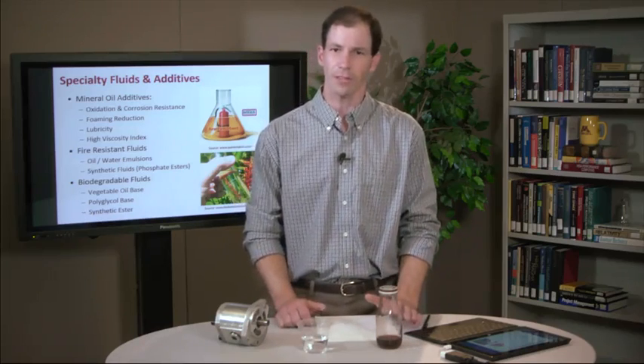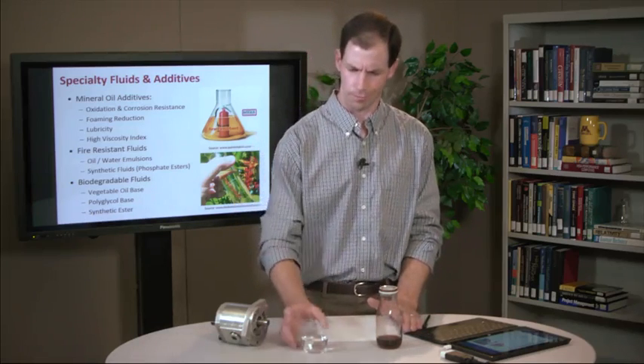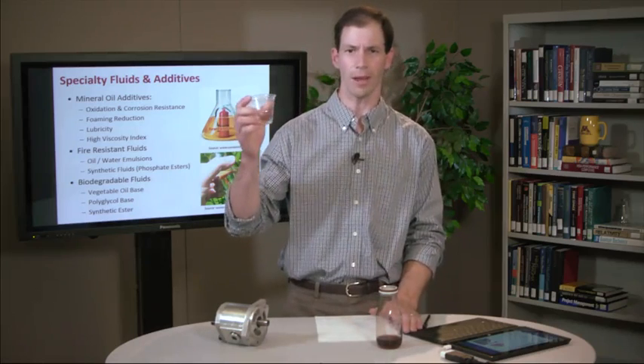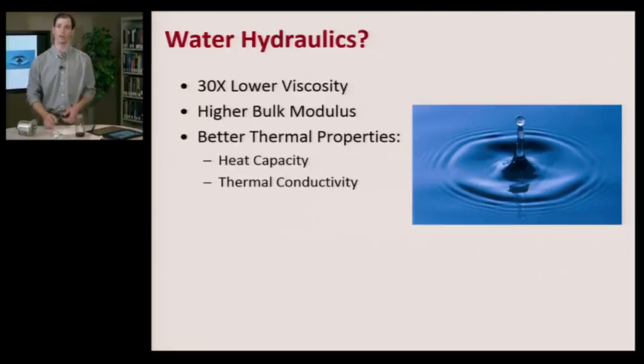So with that said you might start thinking why not use this? Why not use water as the hydraulic fluid? It has a lot of great properties. First of all it has a very low viscosity which means low pressure drops through our components. One problem with a low viscosity fluid is it's difficult to seal and so we have to tighten up the clearances that we're sealing on.